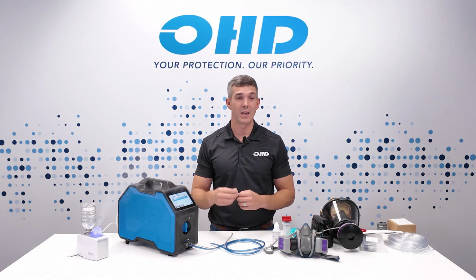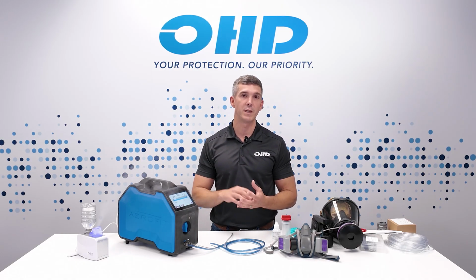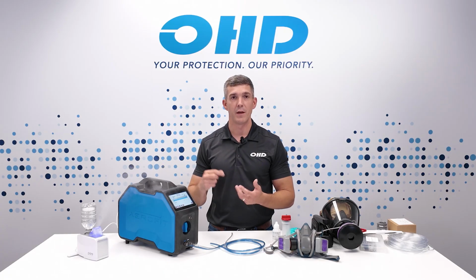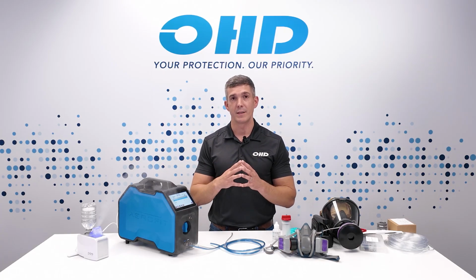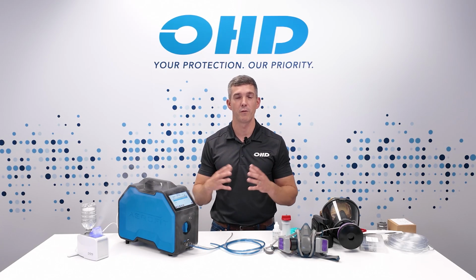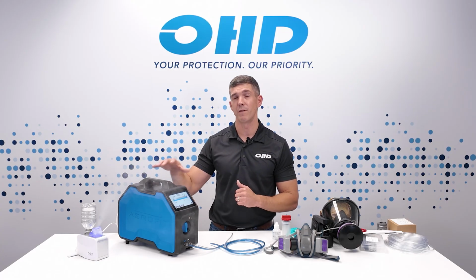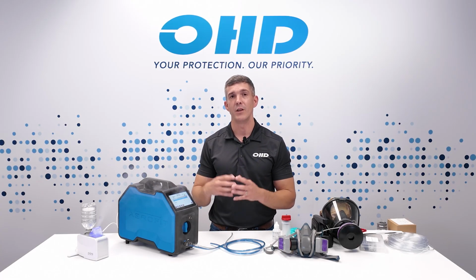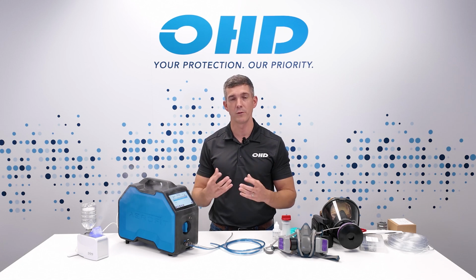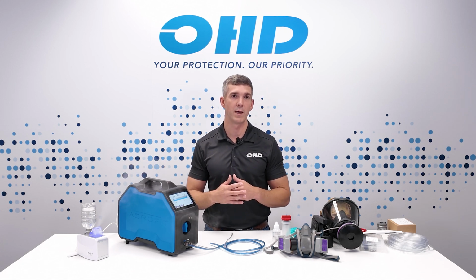The other important thing is that your alcohol wick is fully saturated. So make sure that your alcohol wick allows that time that we mentioned earlier in the training to fully saturate, but also if you've been running fit testing for a number of hours and you see low concentrations or low counts, you might want to saturate your wick again there.